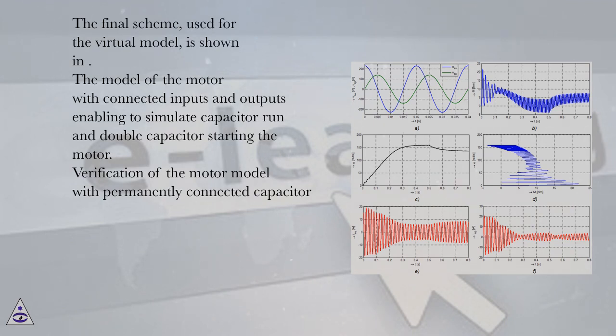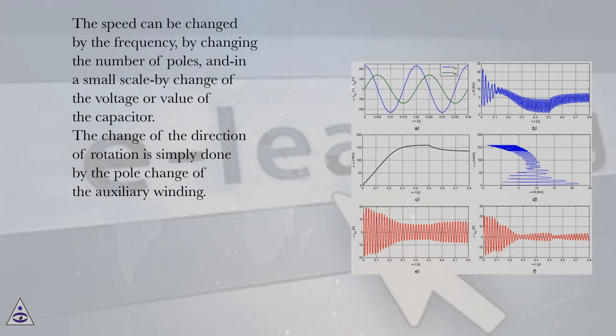Verification of the motor model with permanently connected capacitor. The speed can be changed by the frequency, by changing the number of poles, and in a small scale by change of the voltage or value of the capacitor. The change of the direction of rotation is simply done by the pole change of the auxiliary winding.